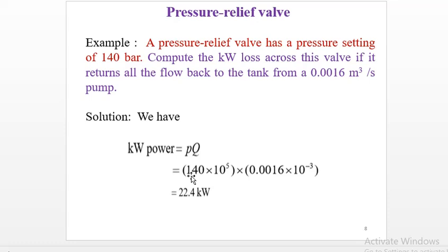Then only we can say that the volume is 0.0016 meter cube per second and 140 bar pressure can be developed, and at the prime mover end it will consume 22.4 kilowatt of the power, that is by the consumption of the electricity.